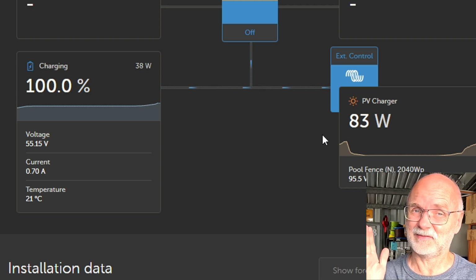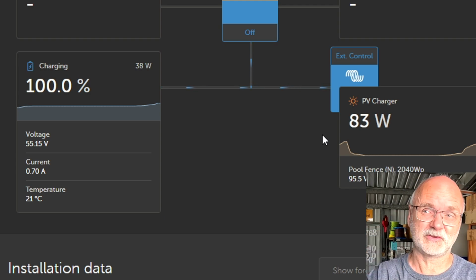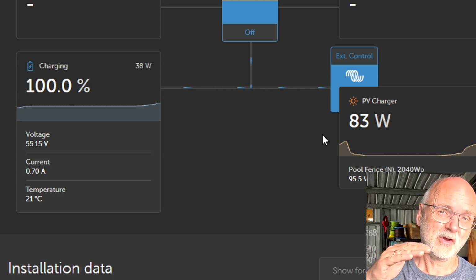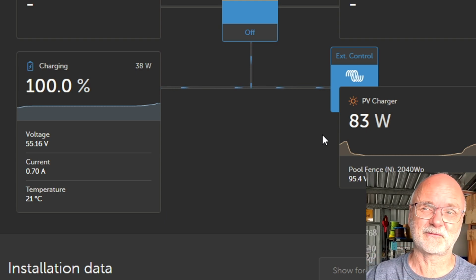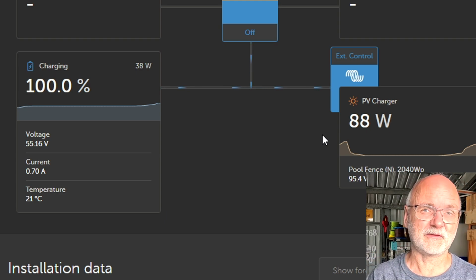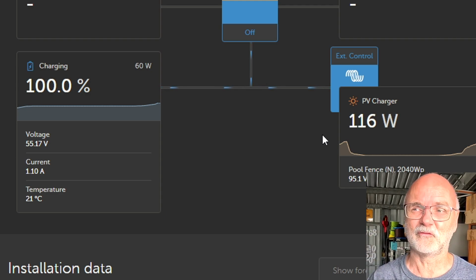And now is exactly the point of time where we should drop the voltage from 55.2 all the way down to 53.6 volts. 3.35 volts per cell keeps them 100% charged, but at a lower voltage level. That's why we do floating with lithium batteries.